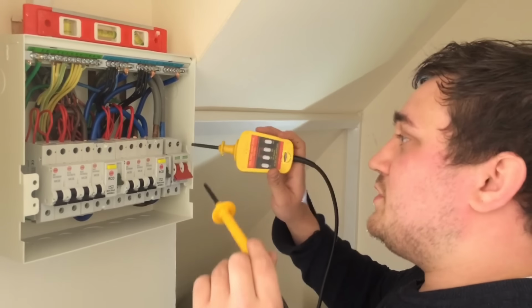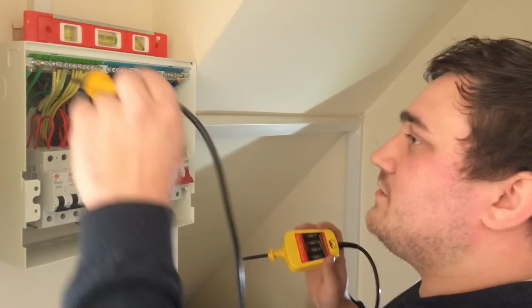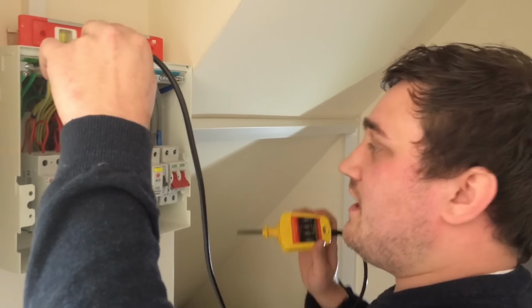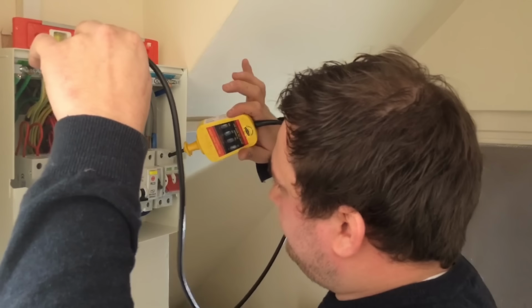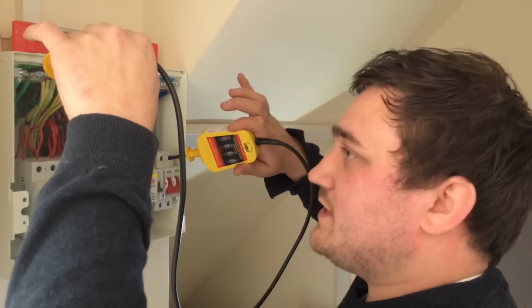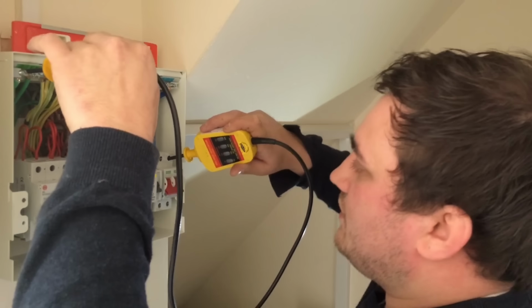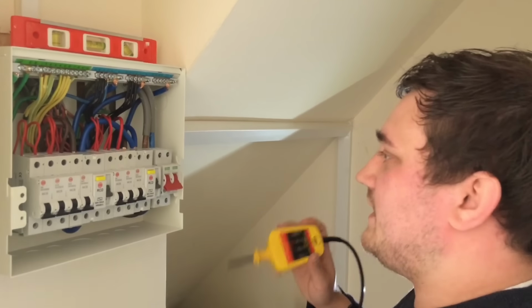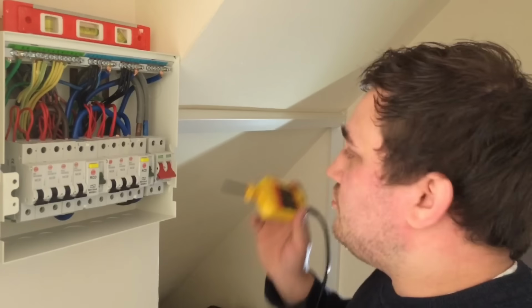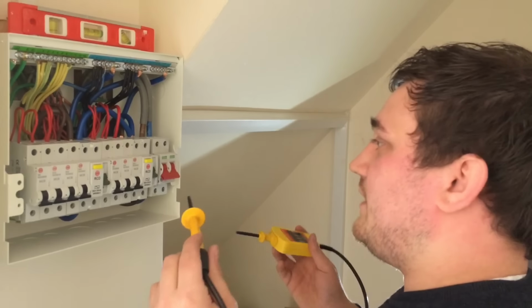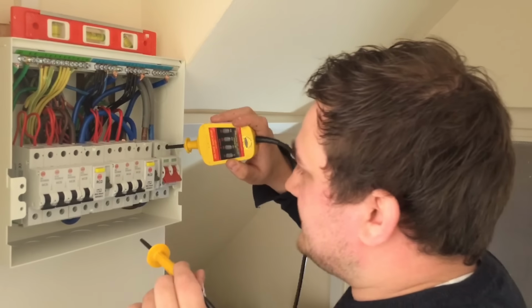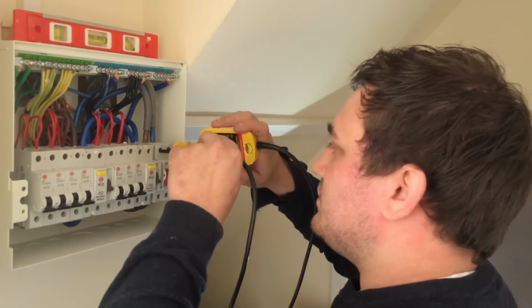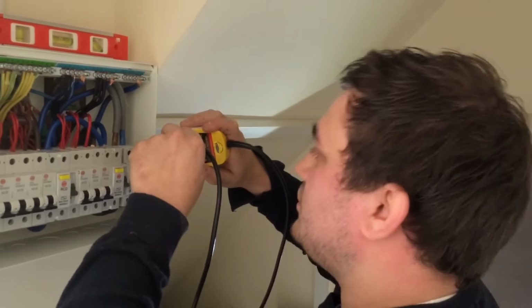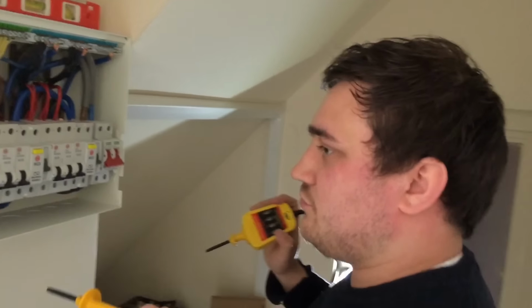Now we're going to do between our neutral and our earth, so we're still going to go on to the least dangerous, which is the earth, and the most dangerous in this case would be the neutral. And we find we have no voltage, which is what we should expect. We're going to come off the most dangerous, off the least dangerous. Now we're going to go between line and neutral at the top of the main switch. We're going to go on our least dangerous first, in this case being the neutral, our most dangerous being the line. We have voltage off of the line and then off of the neutral.